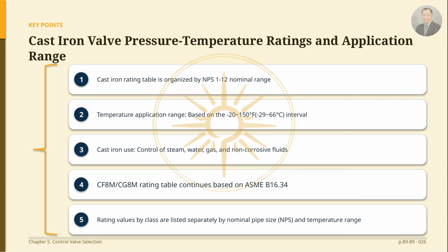Meanwhile, the pressure temperature ratings table for CF8M and CG8M materials continues on the same page, and this table also follows the ASME B16.34 standard. The rating values for each class are listed separately by nominal pipe size and temperature interval.